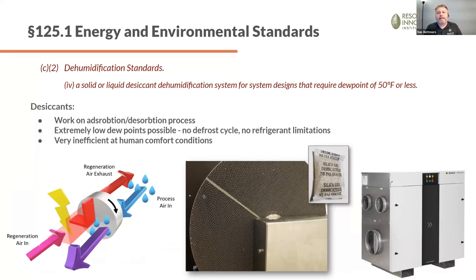The reason being, desiccant dehumidifiers are made for very low dew point, very cold conditions, but they are very inefficient at our normal growing conditions. At 75, 50, they're using 8 to 10 times the amount of energy that a standalone dehumidifier would use.